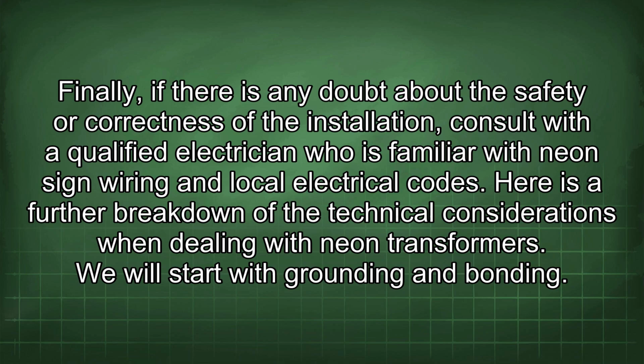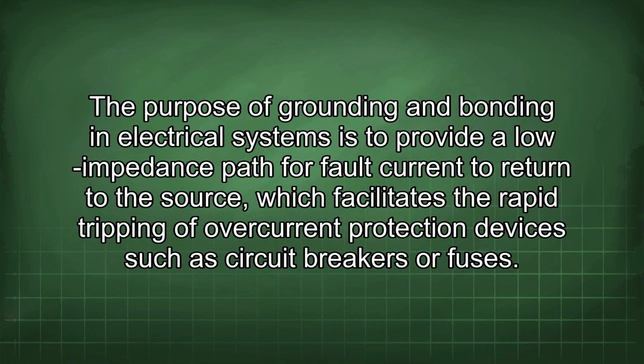We will start with grounding and bonding. The purpose of grounding and bonding in electrical systems is to provide a low impedance path for fault current to return to the source, which facilitates the rapid tripping of overcurrent protection devices such as circuit breakers or fuses.